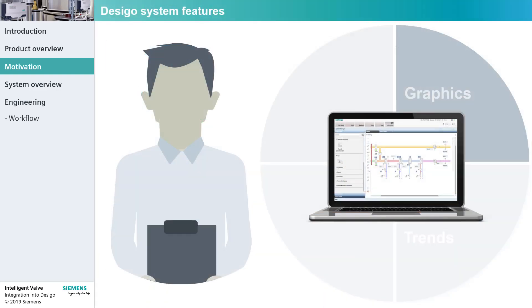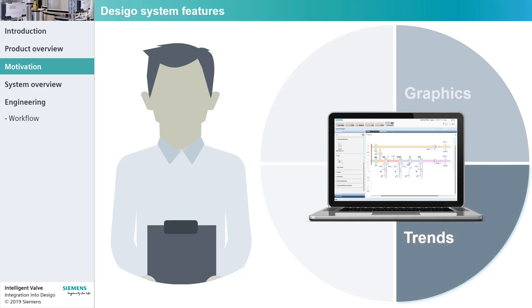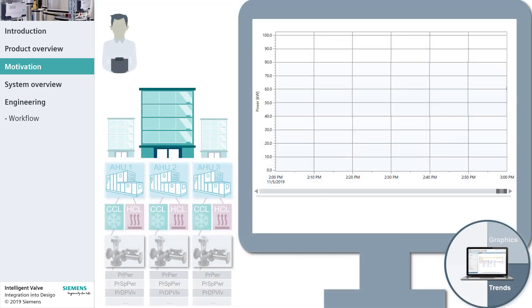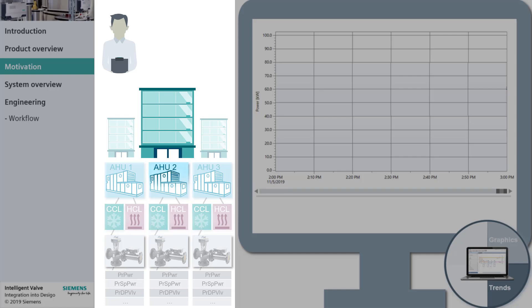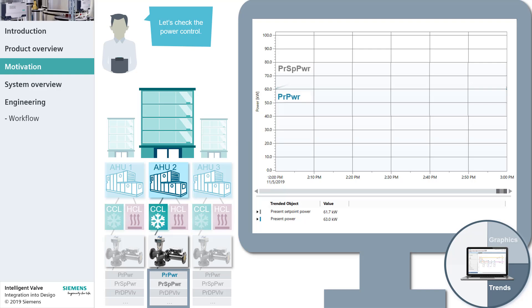Mike obtained a good overview of the operating states. To get more information about the system, Mike starts the Trend application to track data point values or states over time. Mike can do this in several ways. One option is to focus solely on a single intelligent valve and to track several of its data points simultaneously. For example, Mike can verify whether the valve's power control is working as intended. As we can see, the measured power is precisely following the set point. Everything seems to be okay.